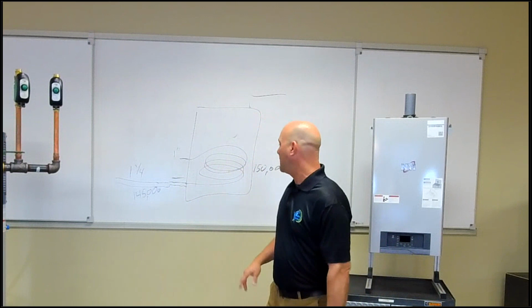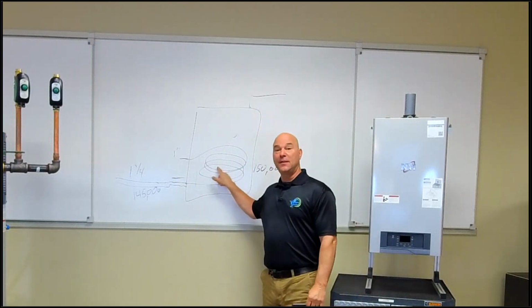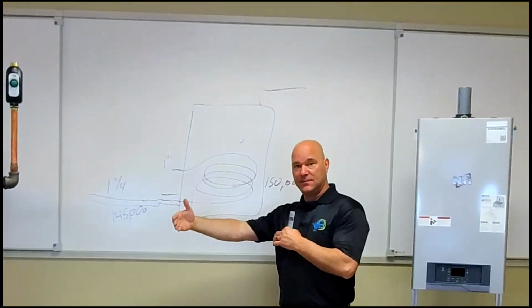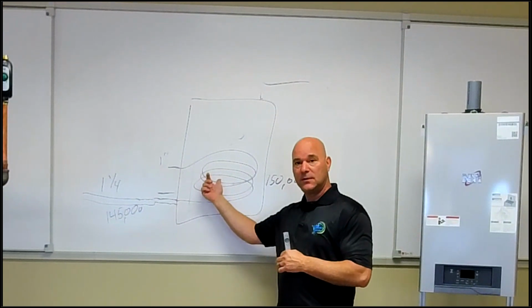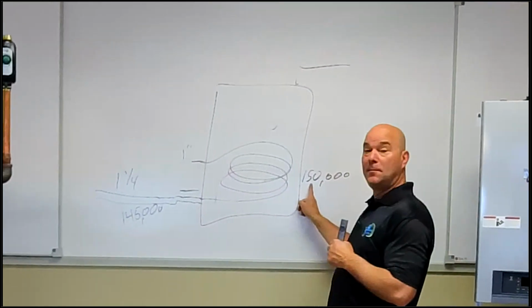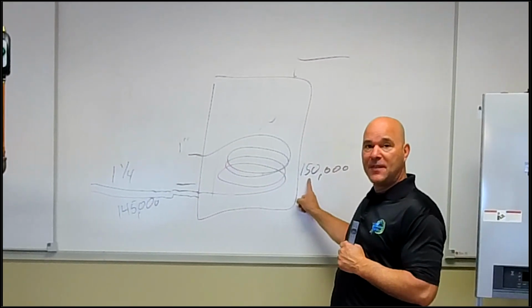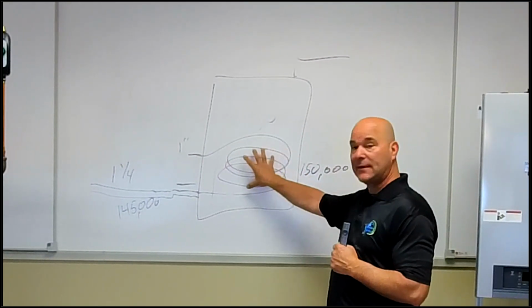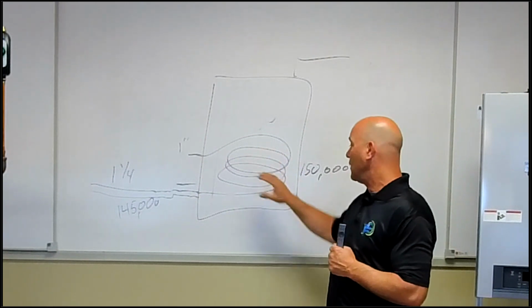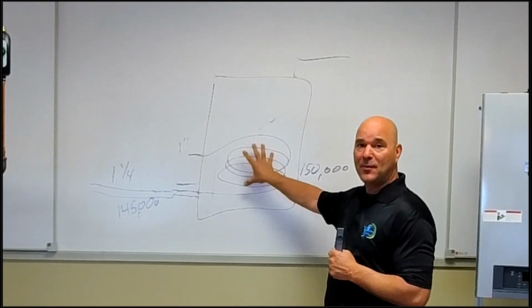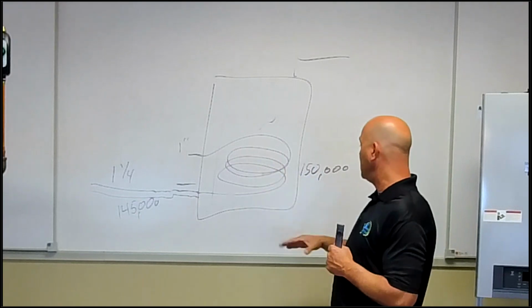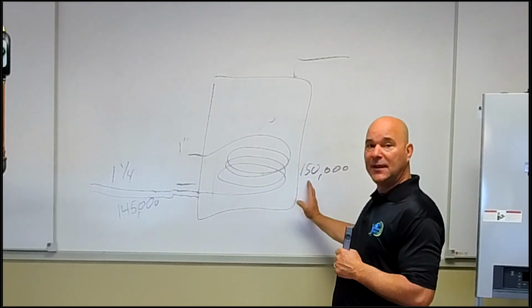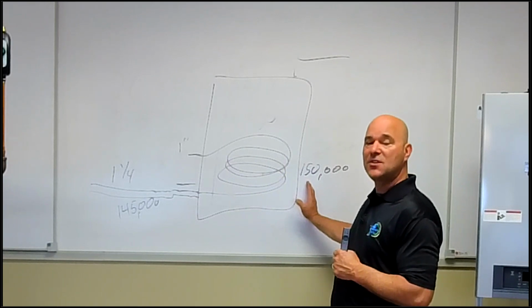How do you size the pump? You need to understand the hydraulic friction of this coil. So we call that head loss. And you would need to know the BTU capability of that indirect, that coil in that indirect. Once you know the head drop of this coil and you know the BTU of the indirect, that will get you going down the road of circulator sizing.